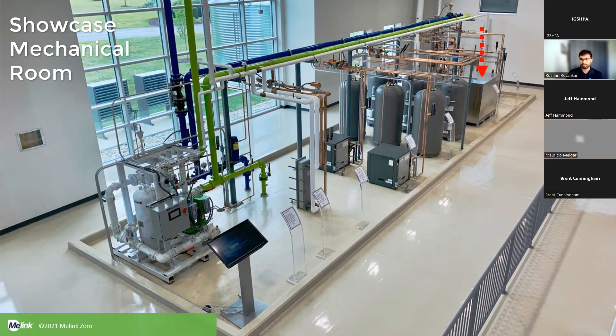Here is a schematic of what I just showed you: 16 heat pumps throughout the building connected with the pumping station to all of these 6 sinks and sources. The baseline is our bore field, which is 4 boreholes at 380 feet, all connected in parallel. Then there are other sinks and sources I briefly mentioned, including an air-to-water heat pump and a water-to-water heat pump connected to a rainwater cistern.